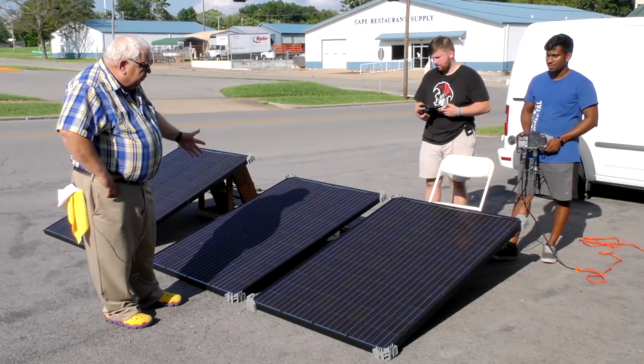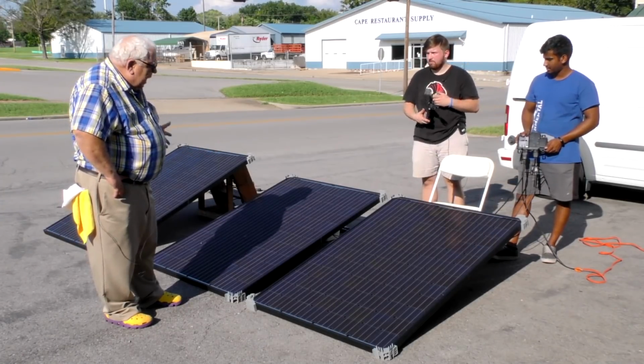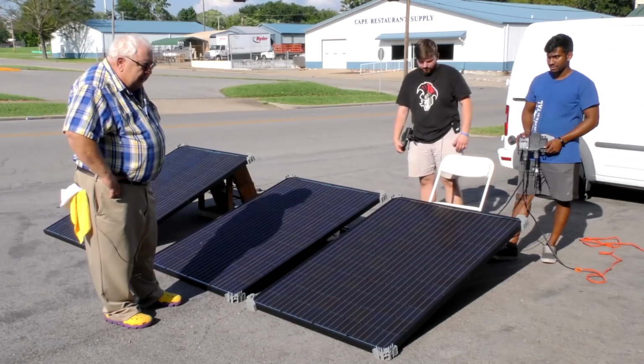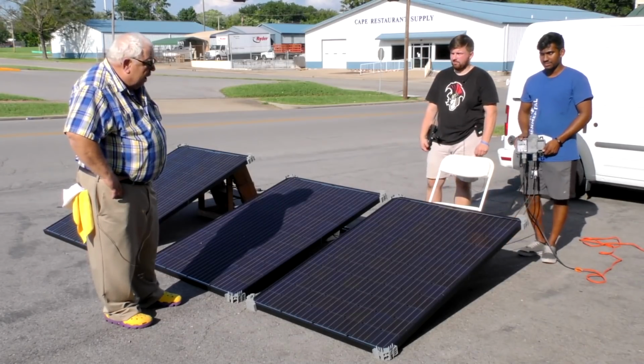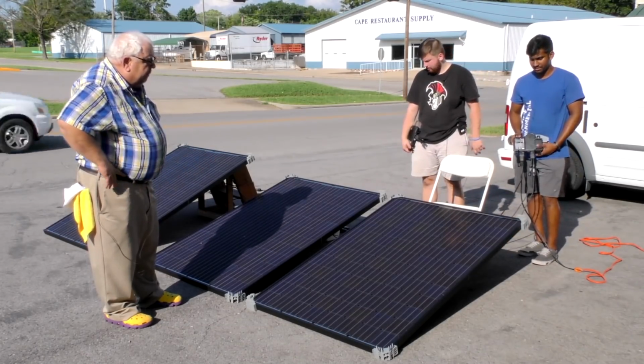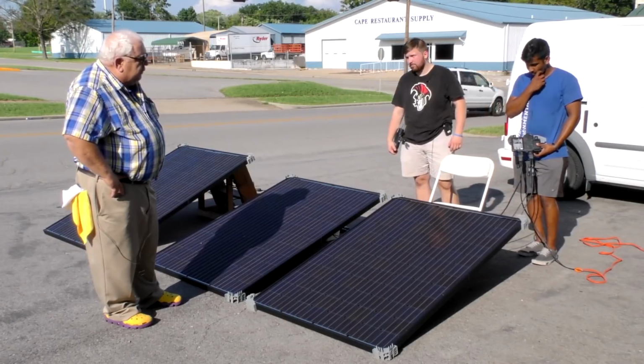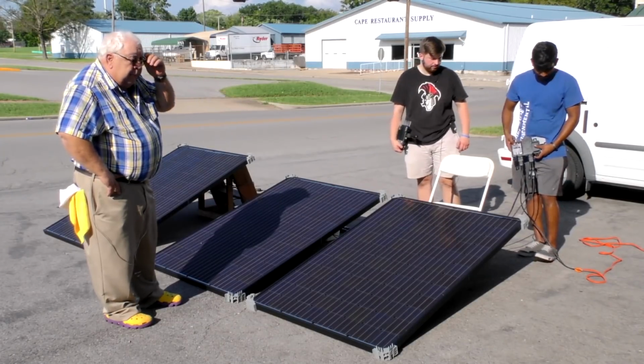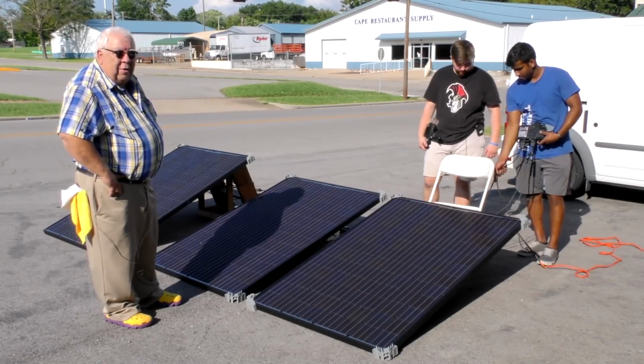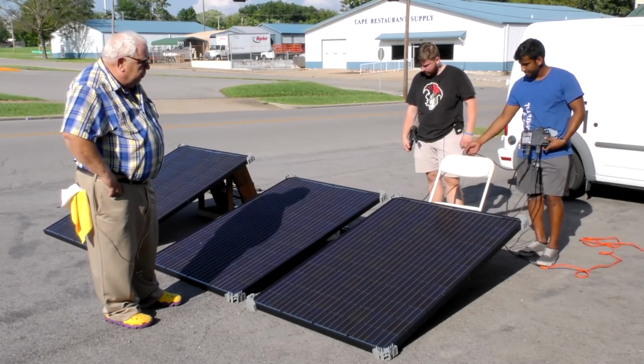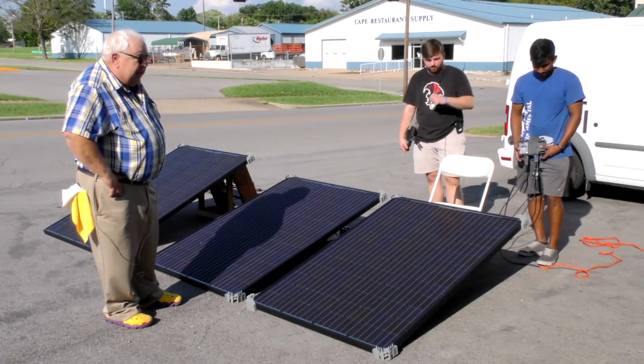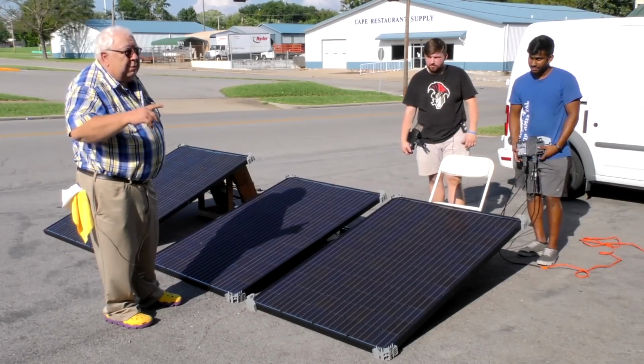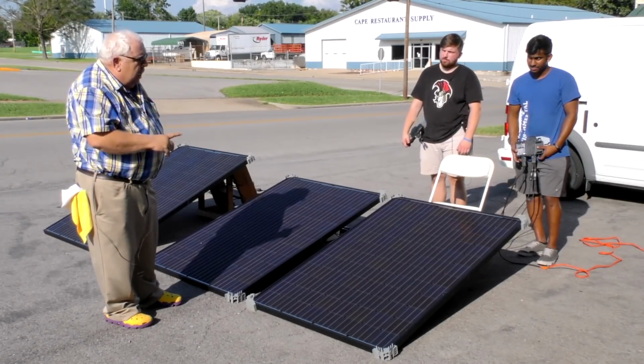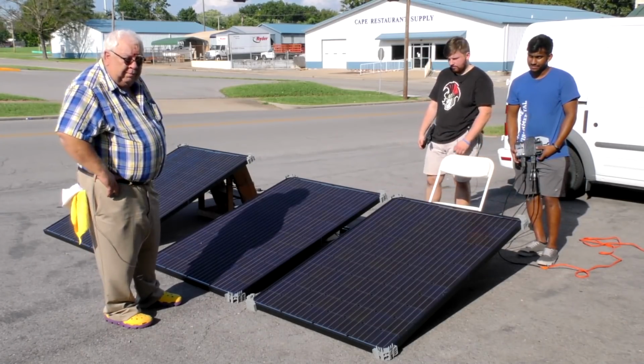I'm shadowing this one, but that won't diminish the output of the MPPT maximum power point tracking on the two that are getting full sun, and they all contribute their AC to our trunk line into the PowerPhase 100 solar input through our charge enable contactor. We should be able to manipulate that contactor and actually turn this off and on.